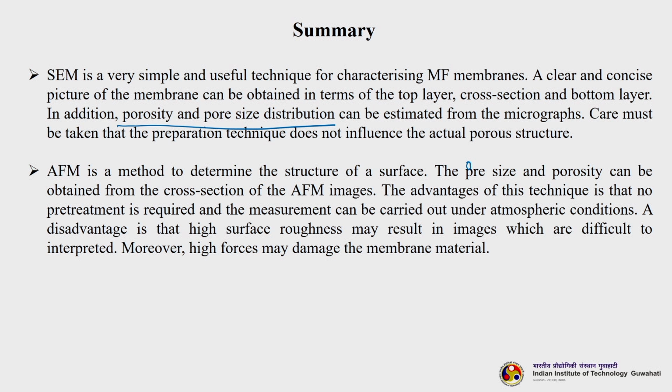A disadvantage is that high surface roughness may sometimes result in images which are difficult to interpret, because the tip is doing the scanning. High forces may get generated, and they may damage the surface. High forces may damage the membrane material, but not all; only a few polymeric materials are susceptible to such damage.